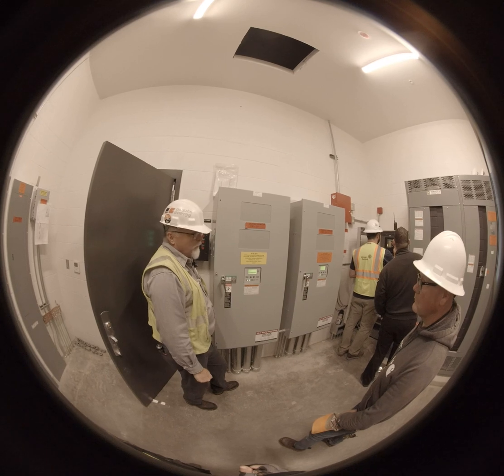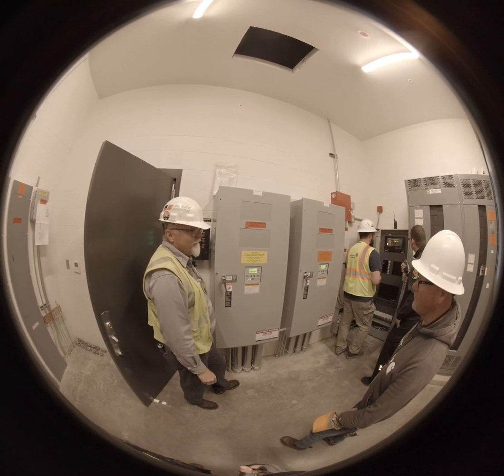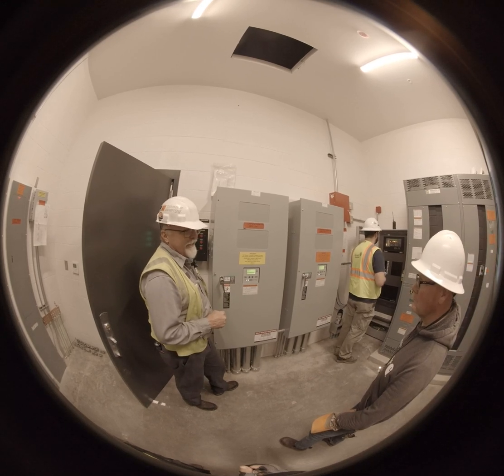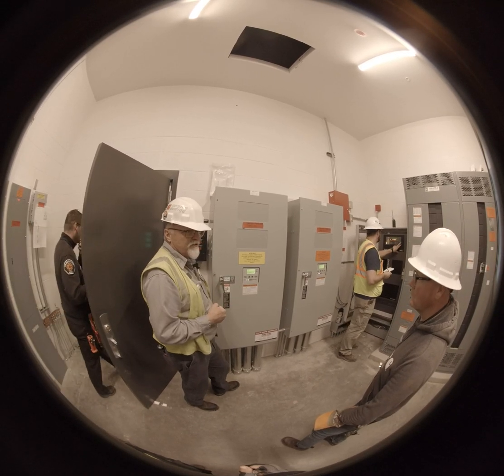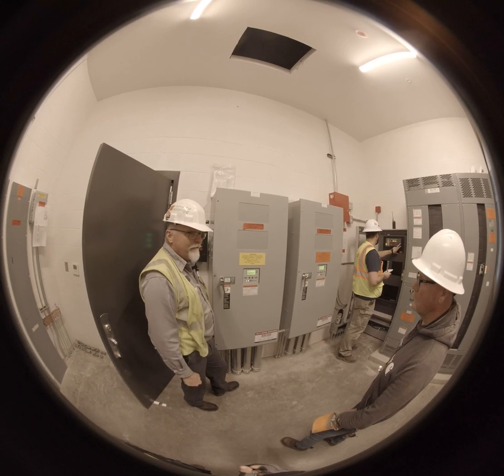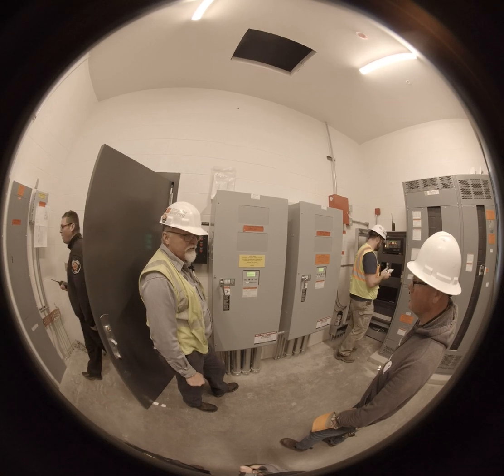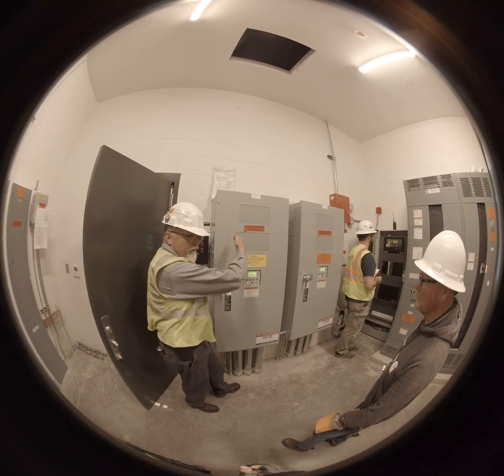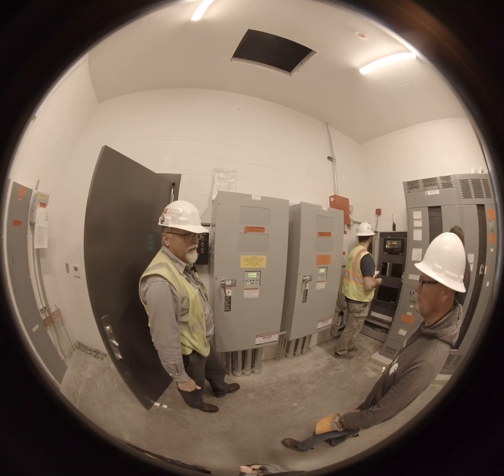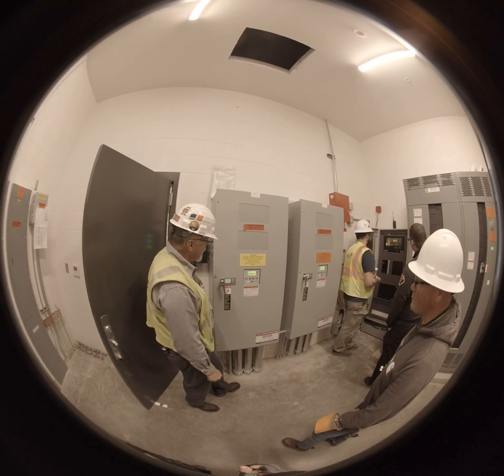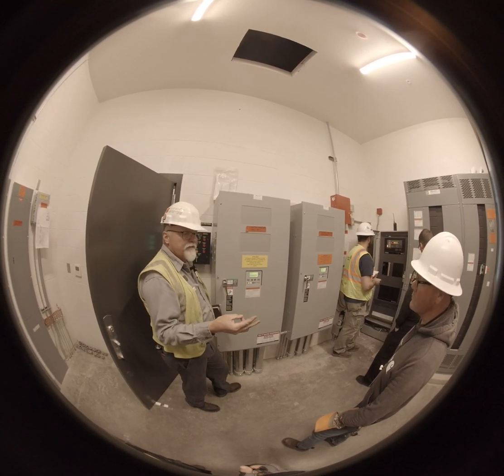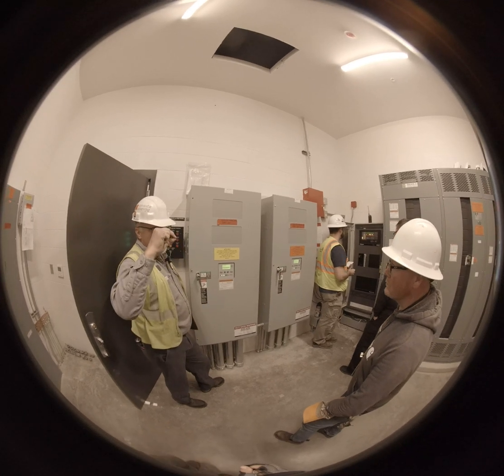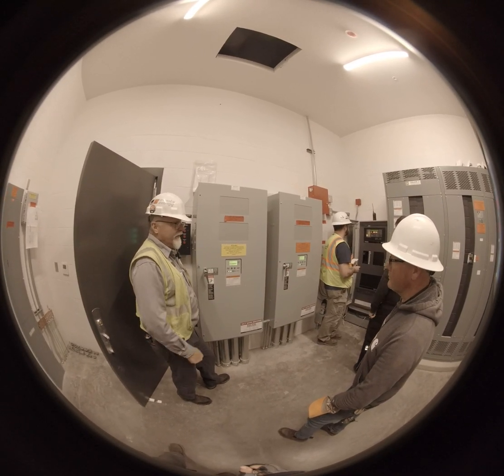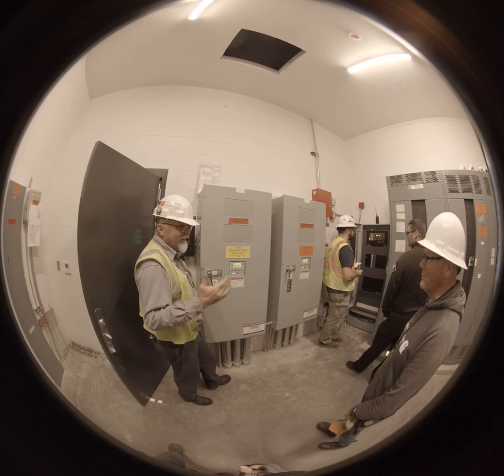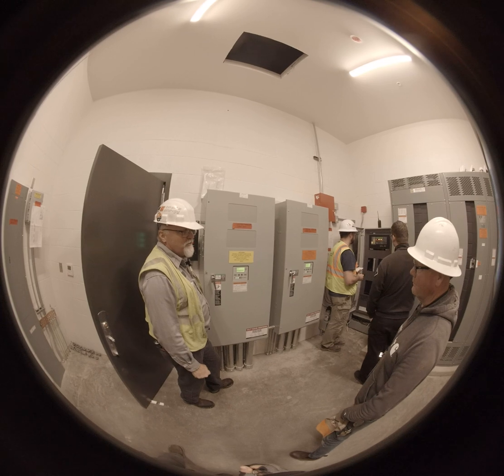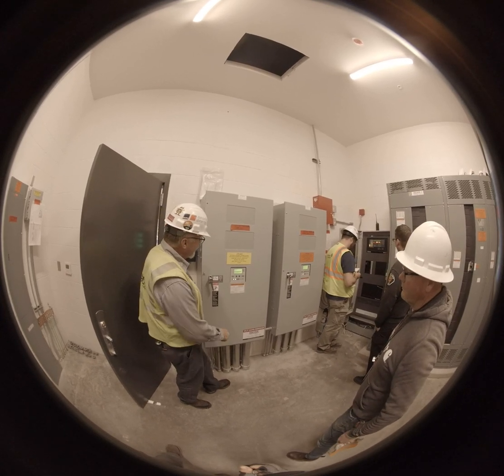You probably don't want to start playing with features, because now you're getting into an area where things can be changed. You can say, I want this as a closed transition transfer switch. This platform is not available as a closed transition. To do that, you have to decouple the two halves so that it can close both together. Then there are your pickup and drop out set points. You can set it so that if the voltage drops, like 2%, it'll start the engine. And that thing will get a lot of hours on it. So like I said, features is not something you want to get into unless you really know what's going on with it.